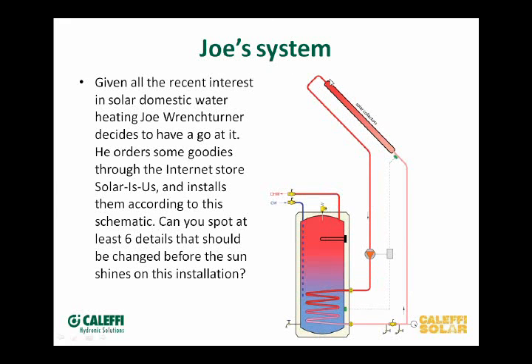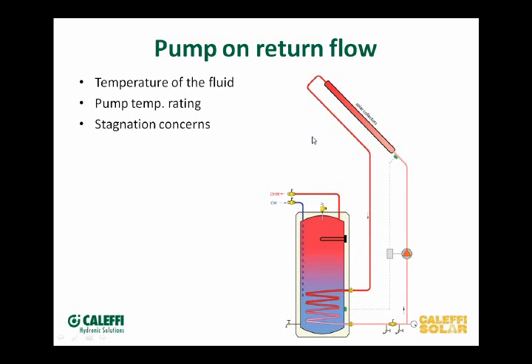In this picture here you'll notice about six mistakes. The first one is the pump on the flow. What you want to do — and here's the mistake drawing — you can see where they've got the circulator, the pump located, coming down from the collector.